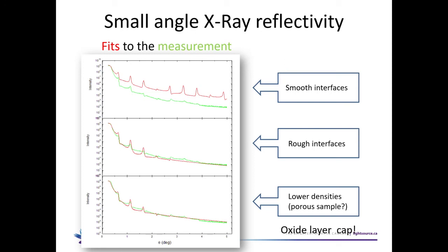You get your measurement and then bring a model — first a very rough model — trying to improve it to make it closer to your sample. In this example, the fit is the red curve and here's the measurement. I can get the periodicity using the formula for D, but if it's not matching I go to the second iteration and maybe add some roughness to the interfaces. In the third iteration, maybe I change the density or add an oxide cap layer. Bit by bit you adjust your model until simulation and measurement have closer resemblance.